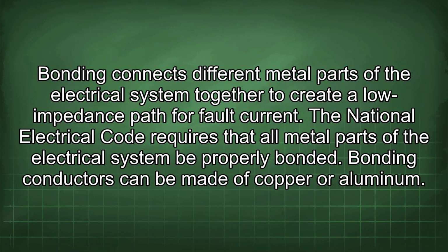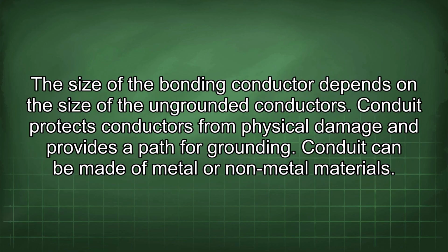Bonding connects different metal parts of the electrical system together to create a low impedance path for fault current. The National Electrical Code requires that all metal parts of the electrical system be properly bonded. Bonding conductors can be made of copper or aluminum. The size of the bonding conductor depends on the size of the ungrounded conductors.